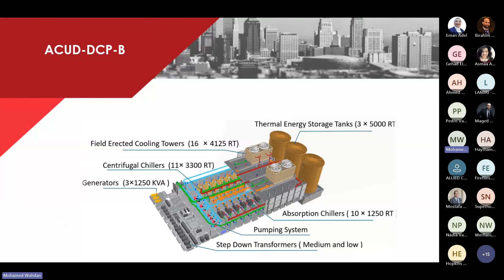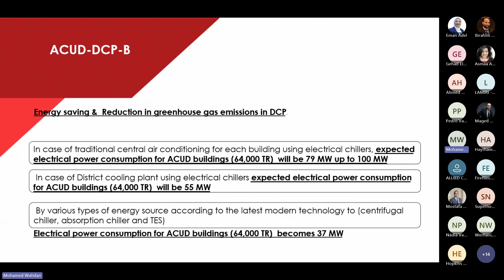Energy saving. If we used traditional central air conditioning with electrical chillers for every building, the energy consumption would be 79 megawatt to 100 megawatt according to the efficiency of each chiller of each plant, which uses water cooled or air cooled condensing. If we use electrical chillers only in the plant, the consumption will be 55 megawatt, so we reduce the consumption from 79 to 55. If we use the combined system of centrifugal chillers, absorption chillers and thermal storage tank, the consumption will reduce to 37 megawatt.